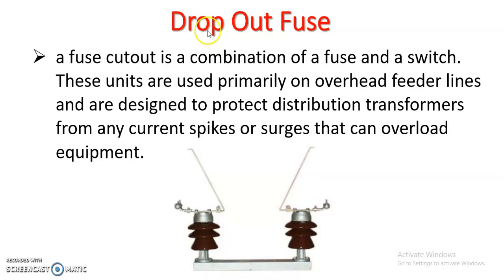Then the next equipment is the dropout fuse, that is the DO fuse. A fuse cutout is a combination of fuse as well as switch. These units are used primarily on overhead feeder lines and are designed to protect the distribution transformer from any current spikes or surges, or overload of equipment. That means if overload occurs or any current spikes or surges occur, this dropout switch will operate, open the circuit, and protect the distribution transformer from further damage.